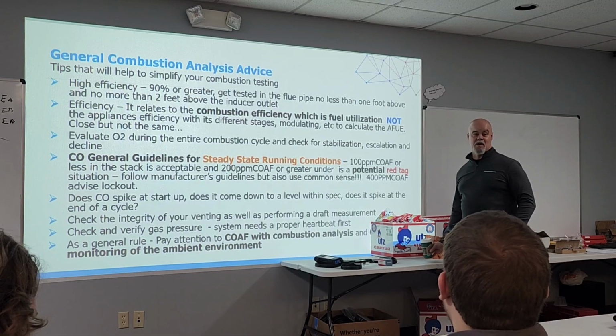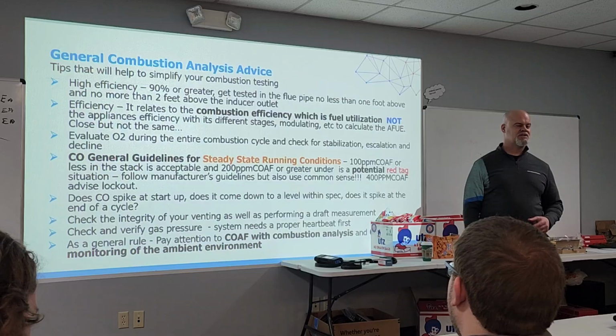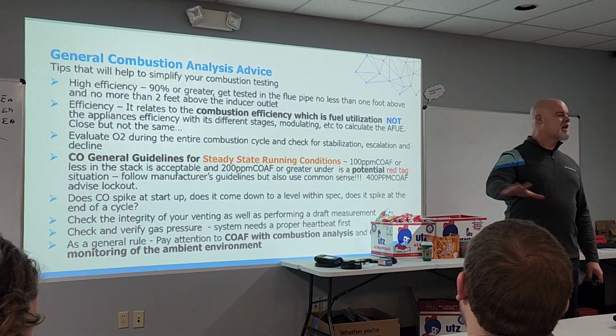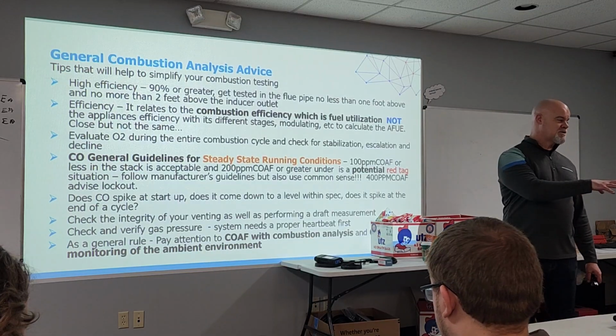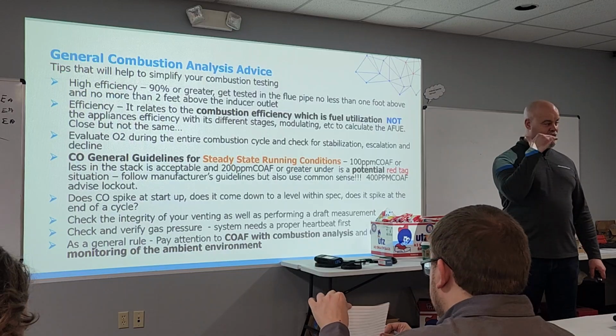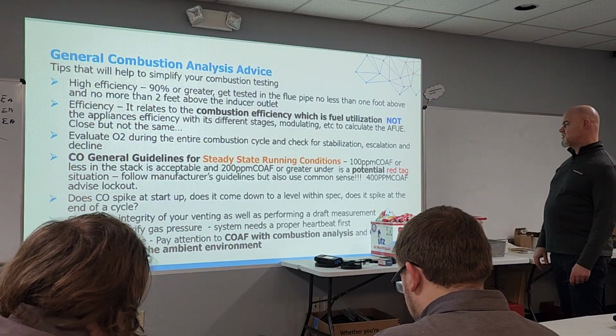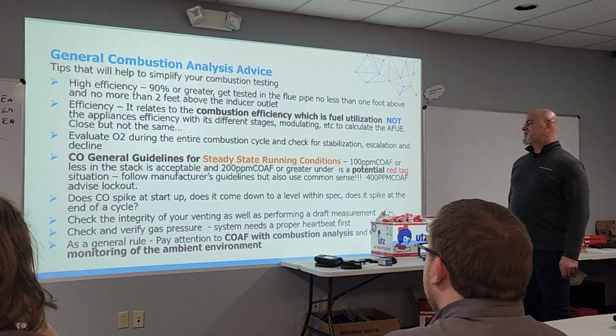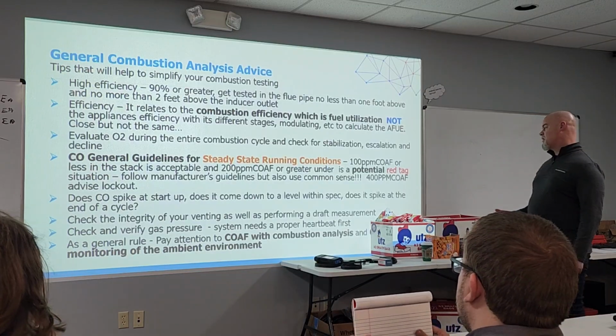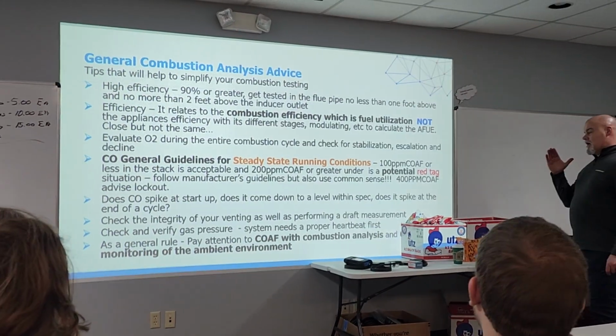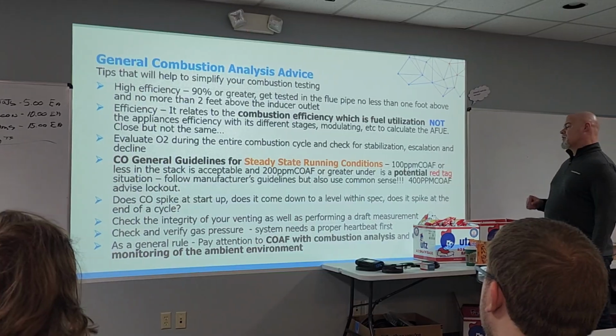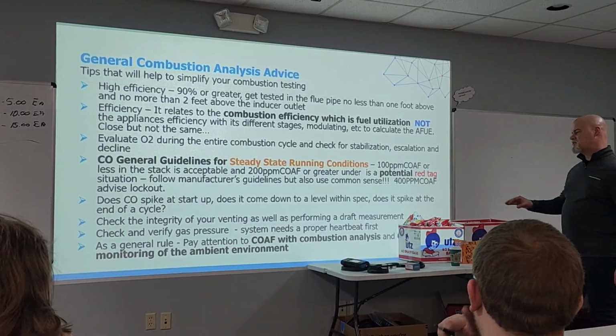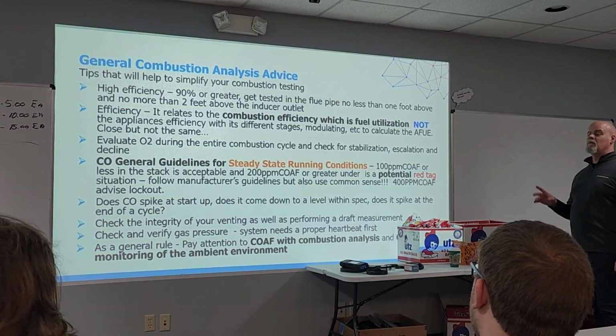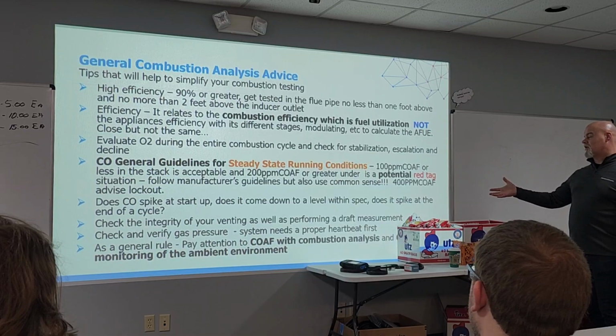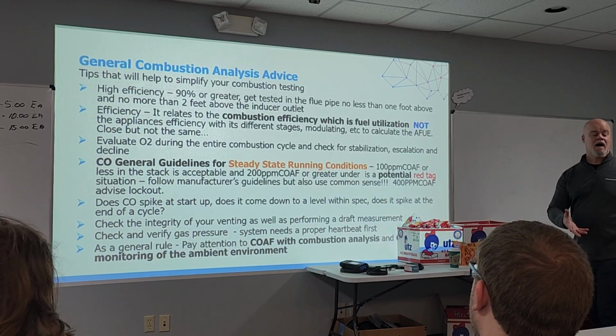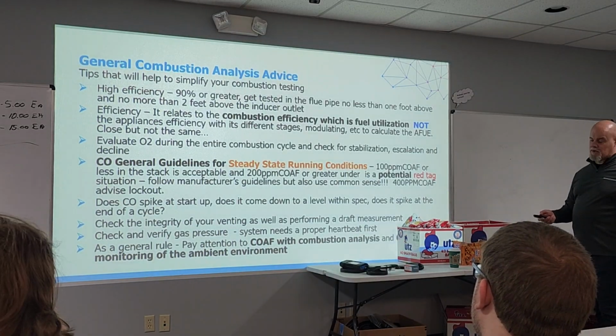So I always go for hell. I'm always going for that worst case situation, because I know if I can control that, I'm not worried about anything else. So I'm always using CO air free for everything. And it's easy for me, with my brain, to focus on that one specific CO number. Does CO spike at startup? Does it come down to a level within spec, and does it spike at the end of a cycle? Check the integrity of your venting, as well as performing a draft measurement. Check and verify the gas pressure. And also, as a general rule, look at CO air free for combustion analysis and regular CO for monitoring. I use CO air free for everything, to your point.